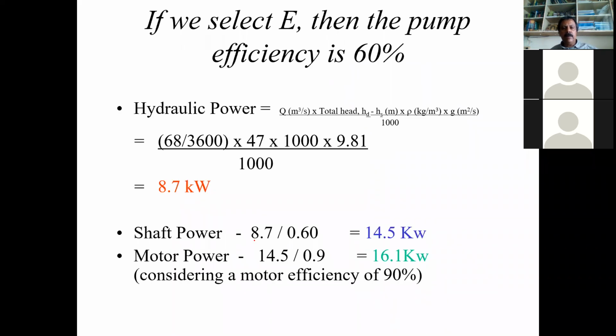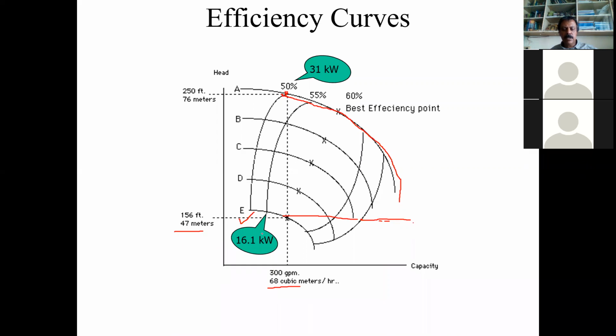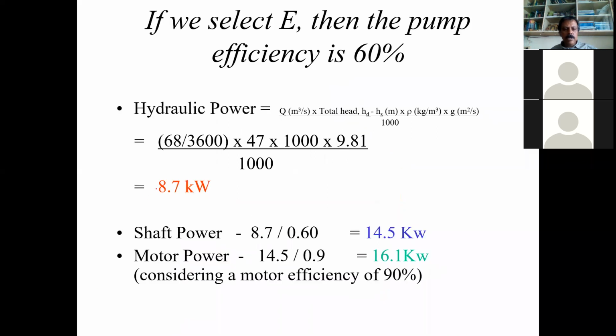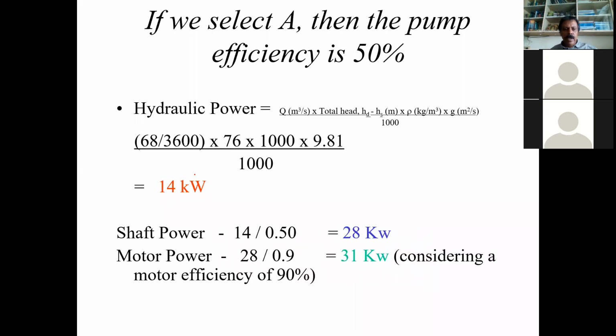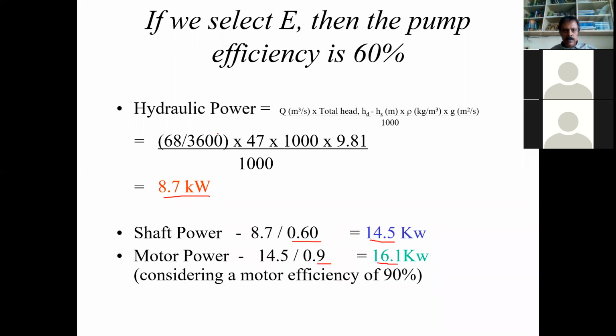So if you look at these calculations, how did we get this 31 and 16 kilowatt? With the equation we have already seen: the flow into total head, into the density, into the gravitational constant, divided by 1000, you get hydraulic power of 8.7 kilowatt. Divided by the efficiency of the pump, you get shaft power, which is 14.5 kilowatt. Divided by the motor efficiency, you get the motor draw of 16.1 kilowatt. Similarly here, everything is the same except for the head. Head here is 76. In the earlier case, the head was 47.